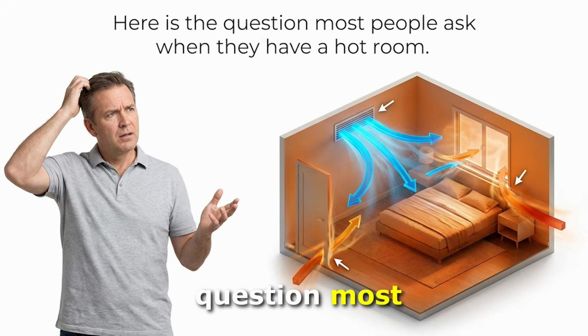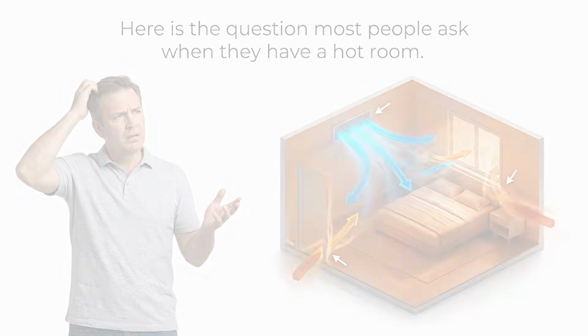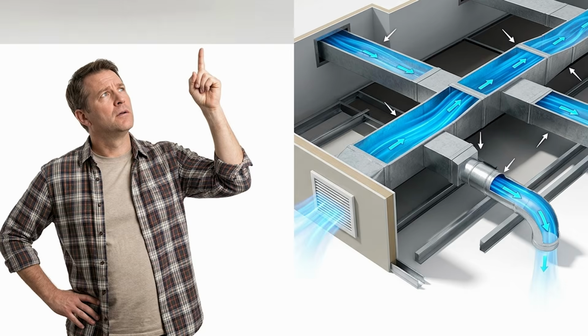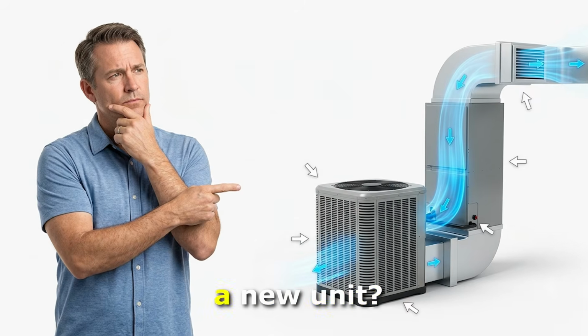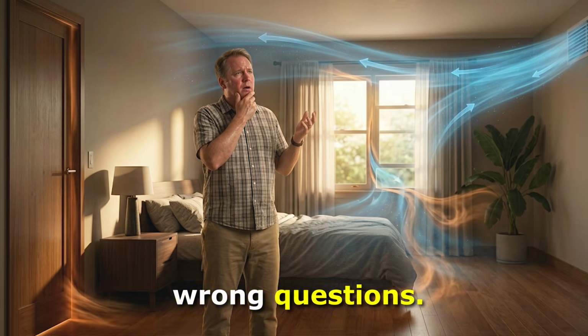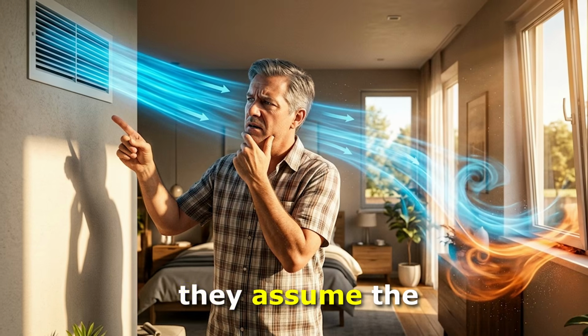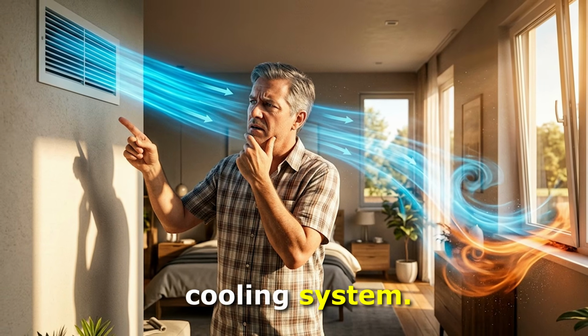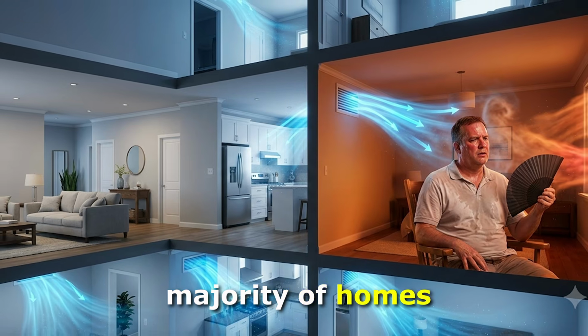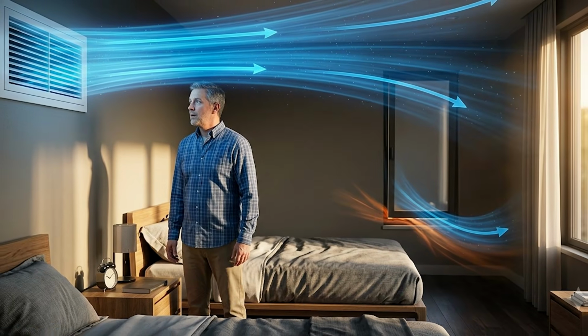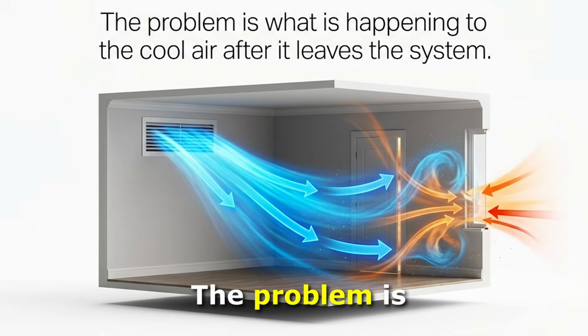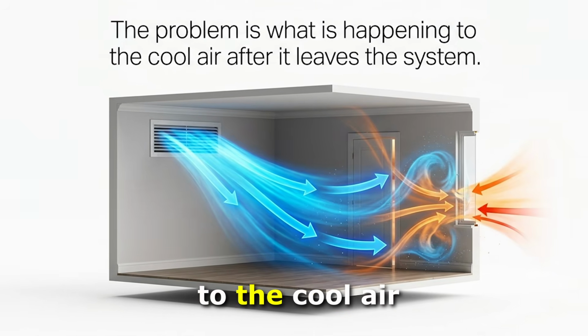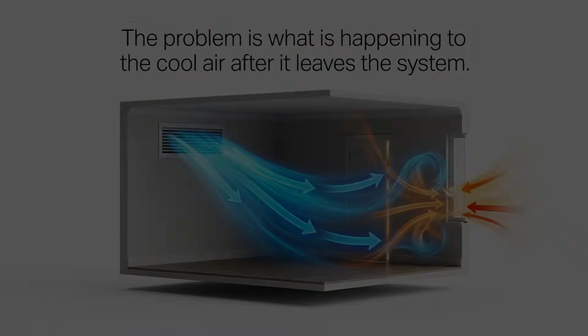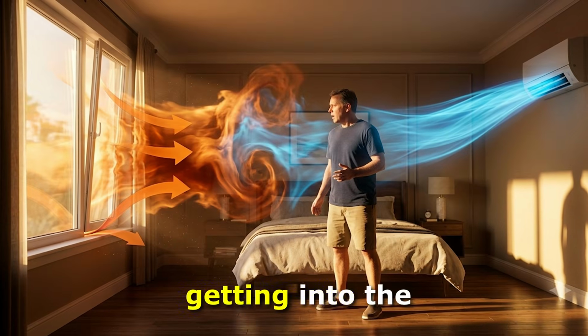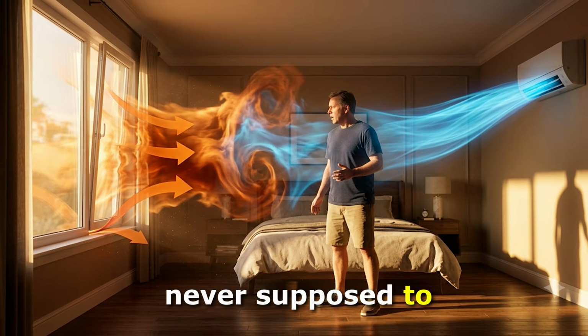Here is the question most people ask when they have a hot room. Is my AC too small? Is the ductwork bad? Do I need a new unit? Those are the wrong questions, and they are wrong because they assume the problem is with your cooling system. In the vast majority of homes with a persistent hot room, the cooling system is working exactly as it was designed to. The problem is what is happening to the cool air after it leaves the system. And the problem is what is getting into the hot room that was never supposed to be there.